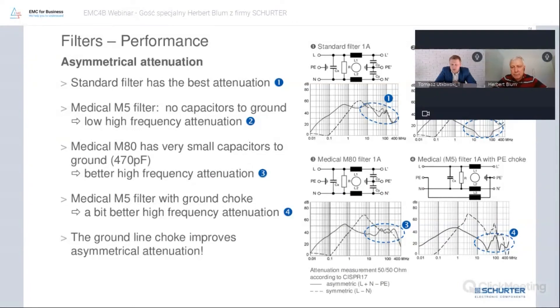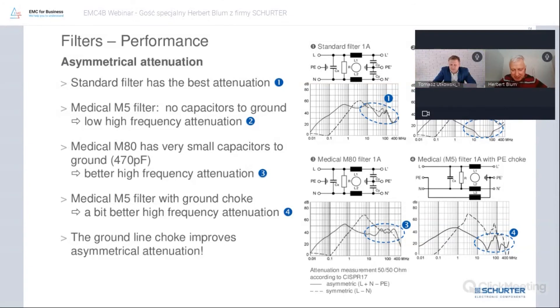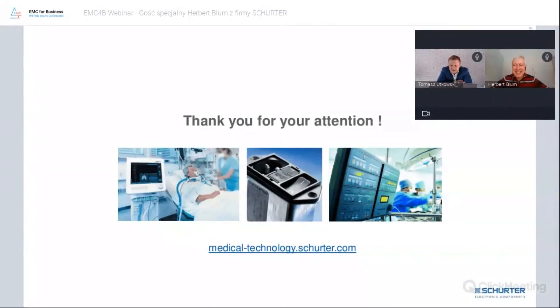We have got a question about the choke on the line: do you select up to the noise level, or is the highest value always the best? The problem is you are not always free to choose any maximum ground choke value, because as I said, the ground choke is normally limited.